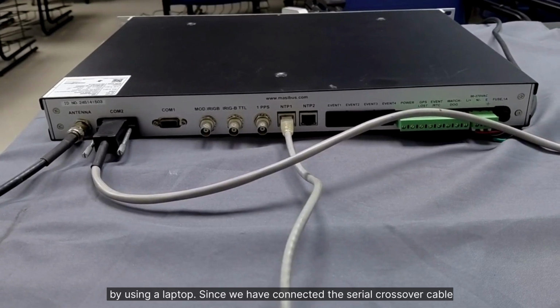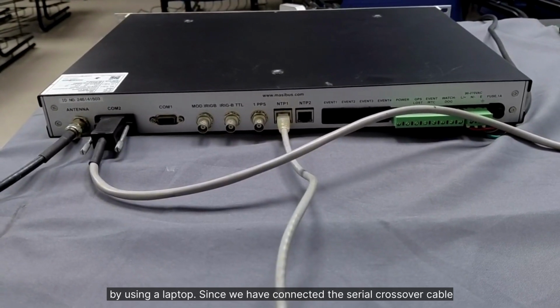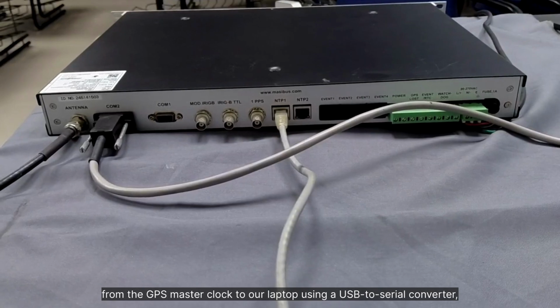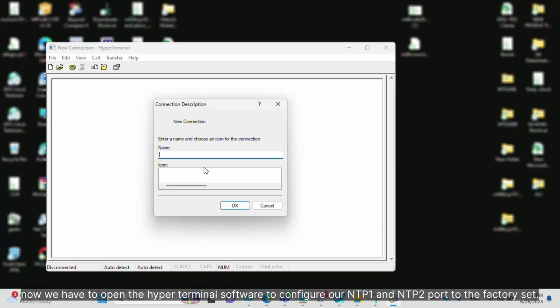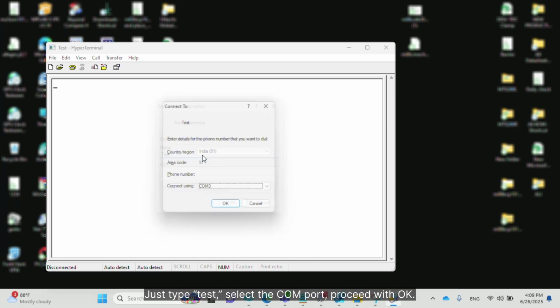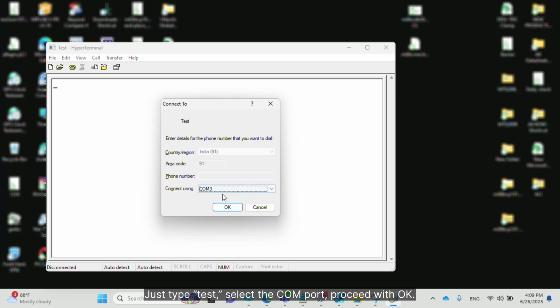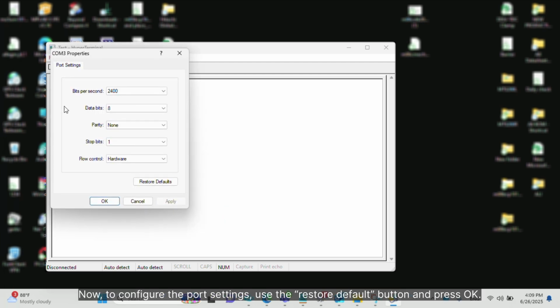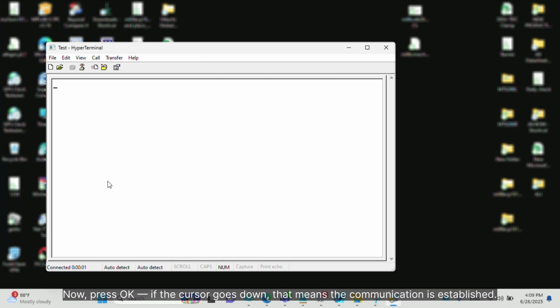So now we will configure the NTP1 and NTP2 port to the default factory set configurations by using a laptop. Since we have connected the serial crossover cable from the GPS Master Clock to our laptop using a USB to serial converter, now we have to open the HyperTerminal software. Just type test, select the COM port, proceed with OK. Now, to configure the port settings, use the Restore Default button and press OK. Now, press OK. If the cursor goes down, that means the communication is established.